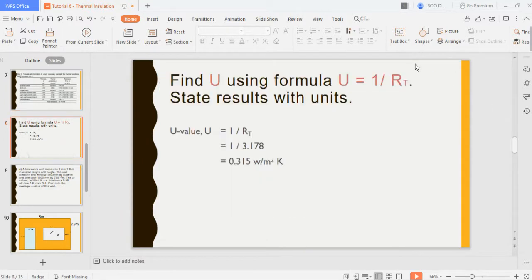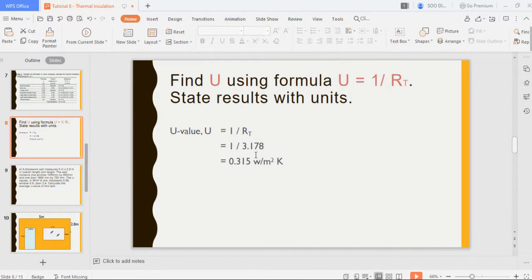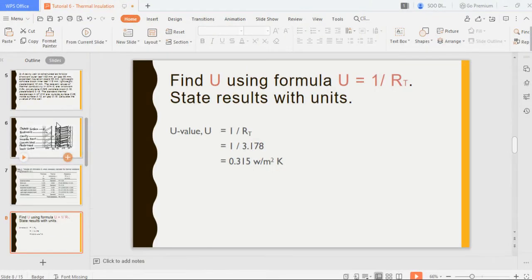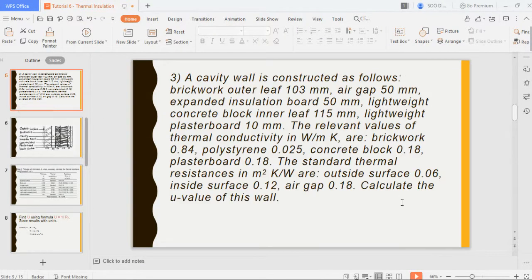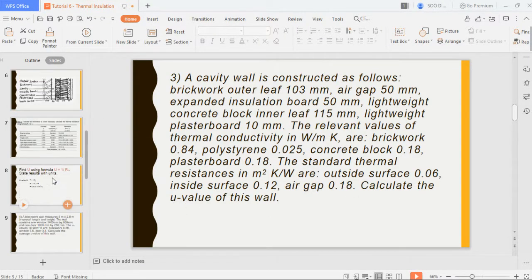Finally, to find the U-value, you take the inverse of the total resistance. U equals 1 over 3.178, giving 0.315 W/m²K. The lower the U-value, the better the thermal insulation. That is how you calculate the U-value of this wall.